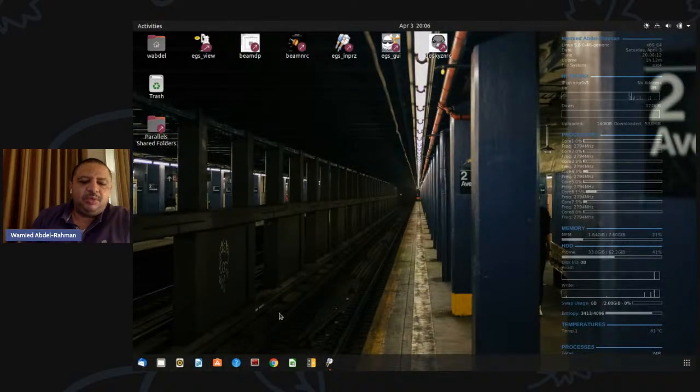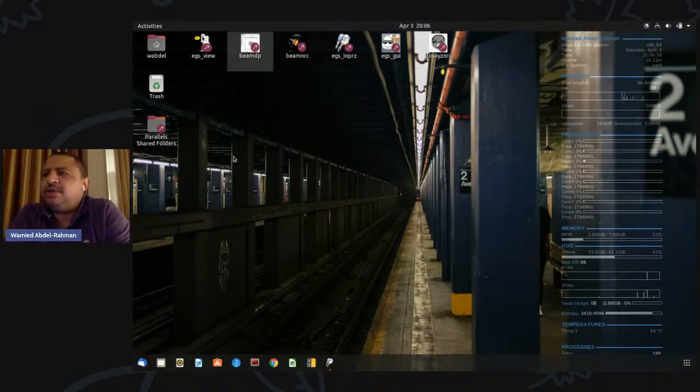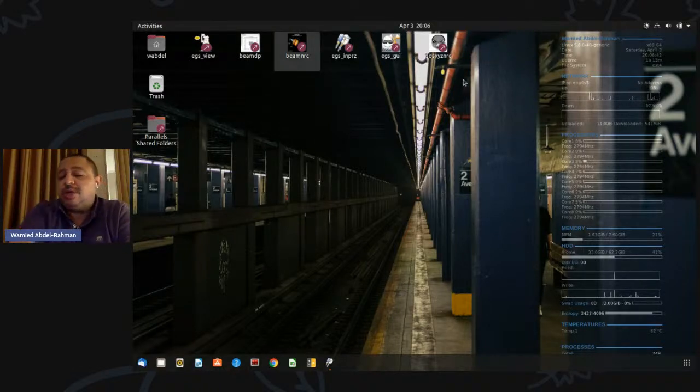Or maybe just let me tell you what I want to do exactly. I want to calculate the KQ for this chamber. For calibration of an external beam, there is an ND factor for the chamber that's usually established in a cobalt beam and provided from a primary standards dosimetry lab, or a secondary lab, an ADCL.